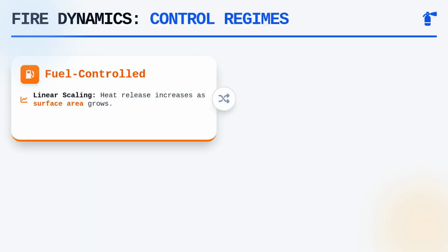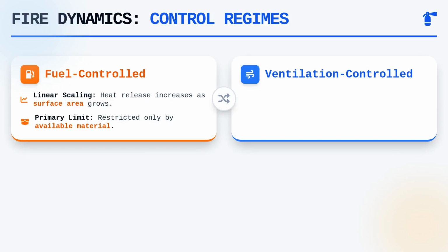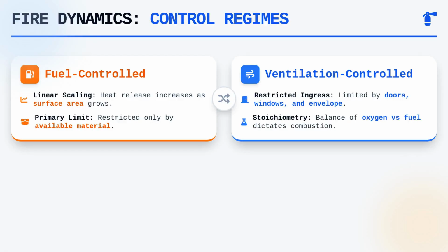The shift between fuel-controlled and ventilation-controlled regimes represents a critical juncture in any fire event, often dictating the success or failure of fire protection systems. A fuel-controlled fire is limited only by the amount of material available to burn, meaning that as we add surface area, we increase the rate of heat release linearly.